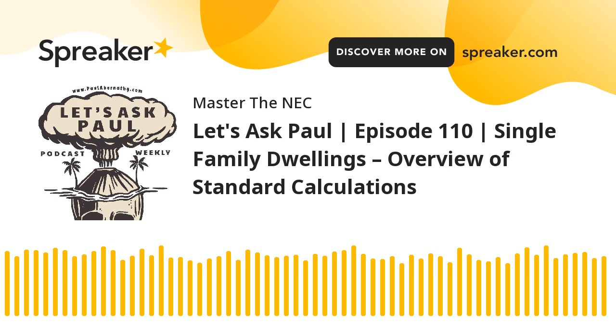If you look at part 3 of Article 220, it says feeder and service load calculations. I mean, that's what we're doing, right? What we did was we started with the pieces under part 2, and we're pulling those pieces. And where do we get the requirements to do that? Basically, it's 220.40. It says the calculated load of the feeder or service shall not be less than the sum of the loads on the branch circuits supplied as determined in part 2 of this article. So we did that, right? We pulled the 220.14(J). We pulled the circuits that were required in 210.11(C)(1), which is back in branch circuits. We pulled all that information together, and now we're combining it all, right?